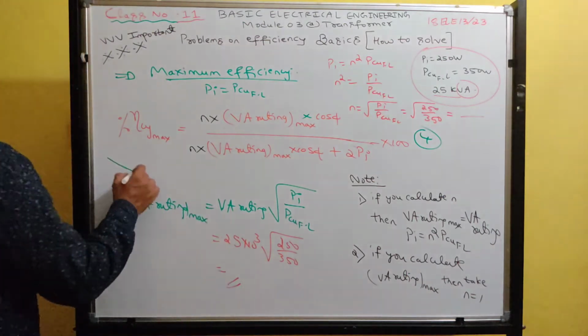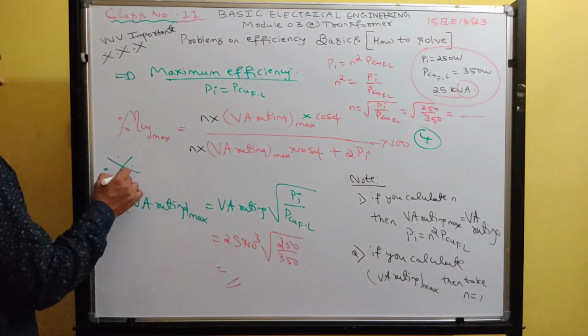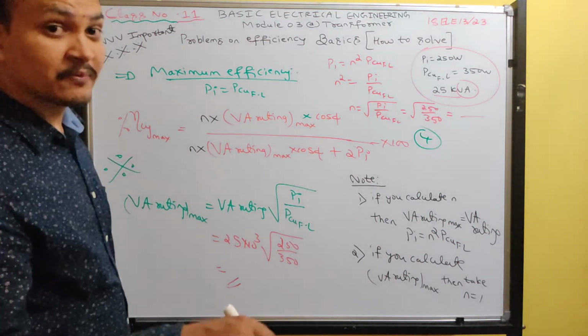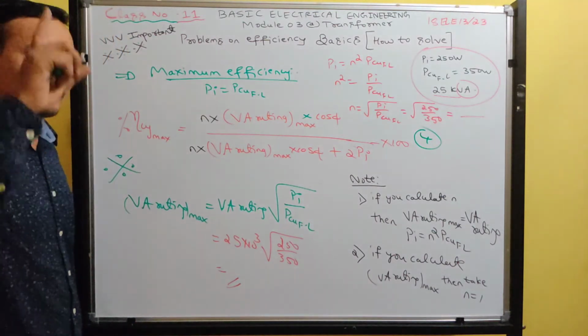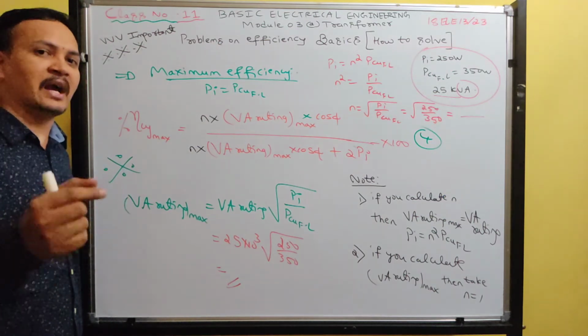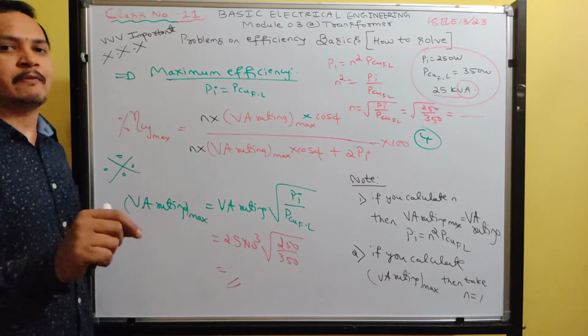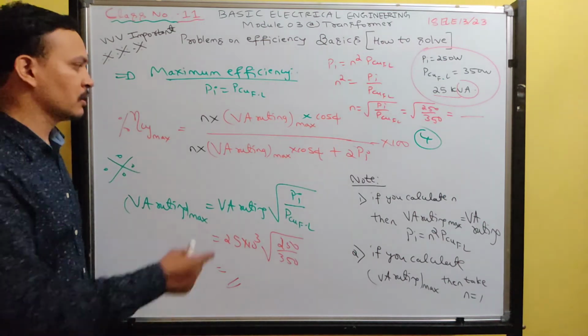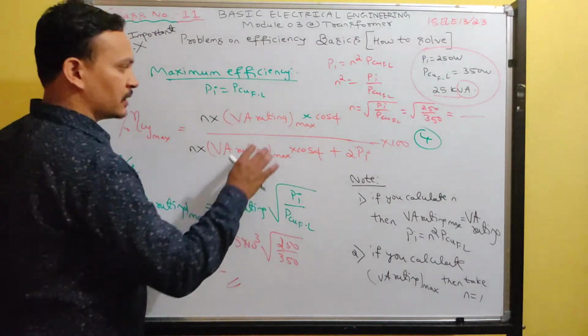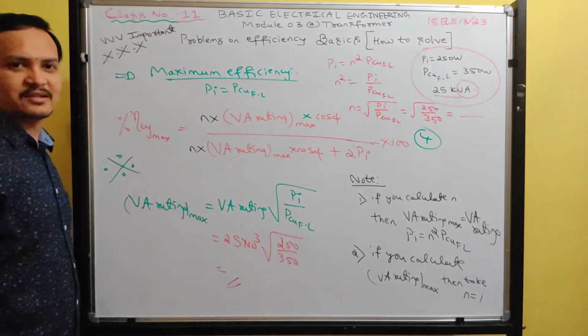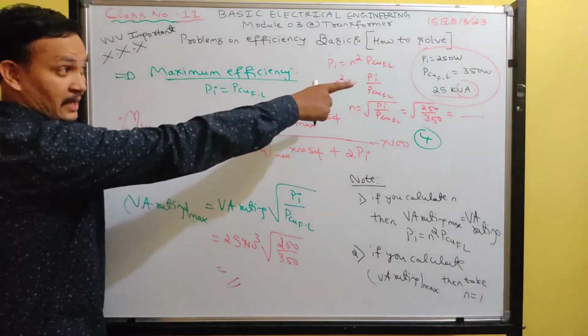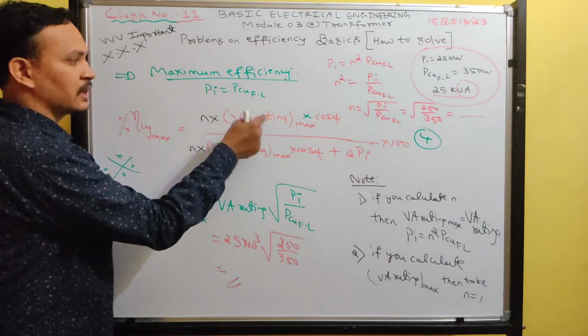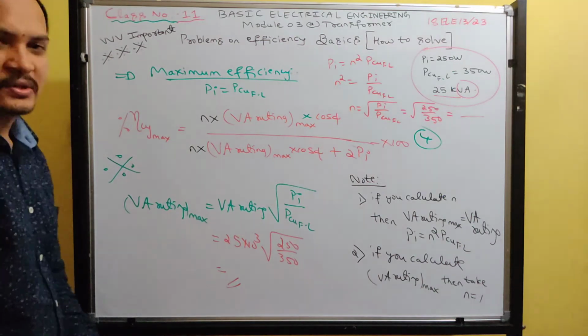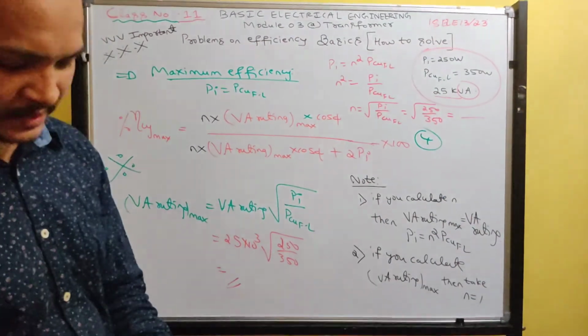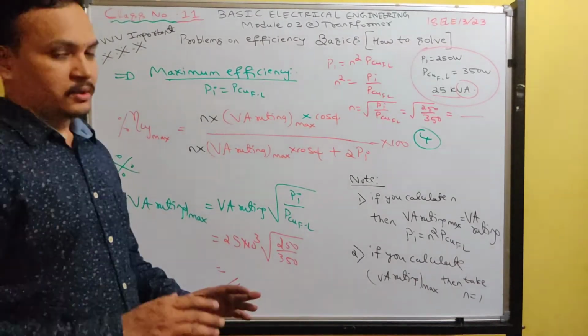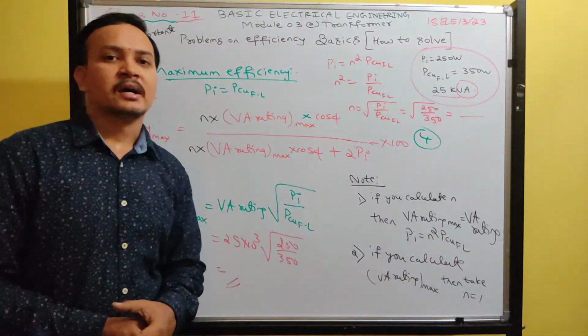Very important, this logic. Most of the students, if they ask determine efficiency and maximum efficiency, they will ask determine efficiency at full load 0.8 power factor, and they will ask determine maximum efficiency at 75% of the load. If they ask 75% of the load, you take directly n is equal to 0.75, but don't calculate VA rating max. If you are given the load, then write directly VA rating. If you calculated VA rating max, then take n is equal to 1. So guys, this completes a strong basics on how to solve problems on efficiency of a transformer.